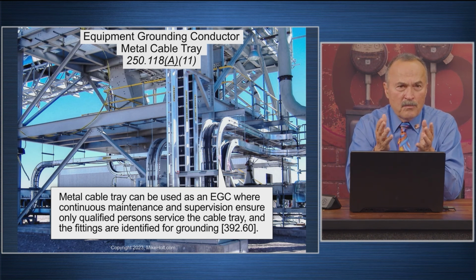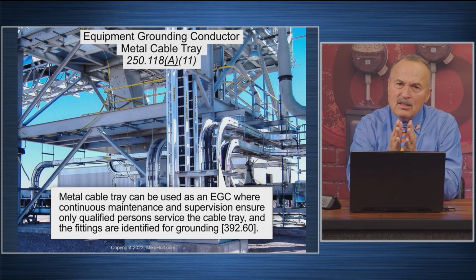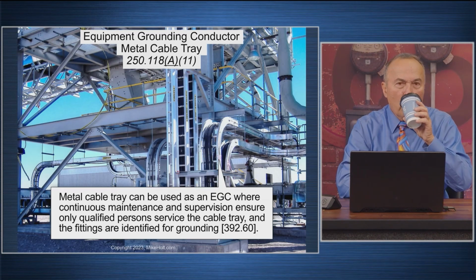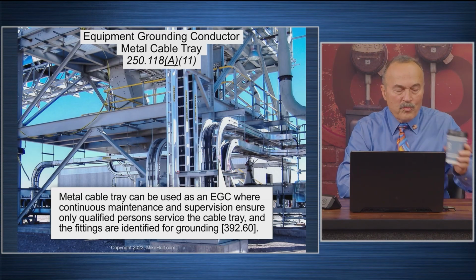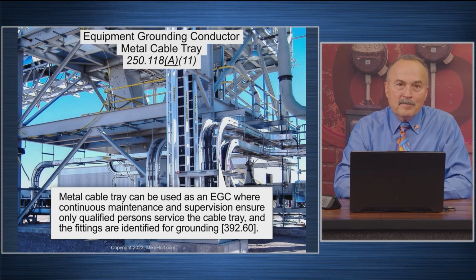Eric, now you have to have special cable tray. This is not any cable tray. Eric, is this done in reality using the cable tray? We never did it, and when I worked for the chemical plants, we never did it because it's too much of a hassle. Cable trays usually run long distances. You have expansion joints, you've got to bond around those. You've got discontinuities. It's just, nah, we're not going to do it.